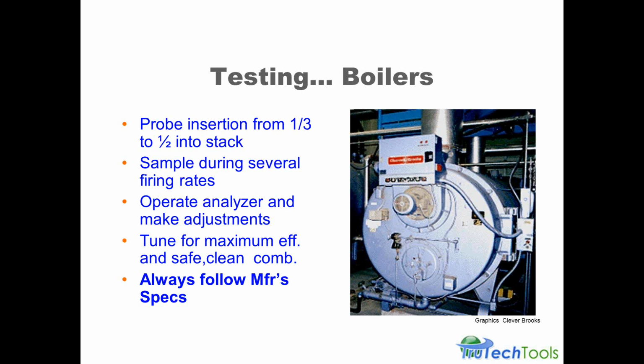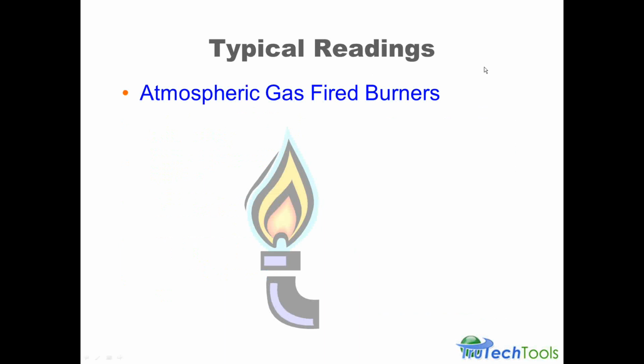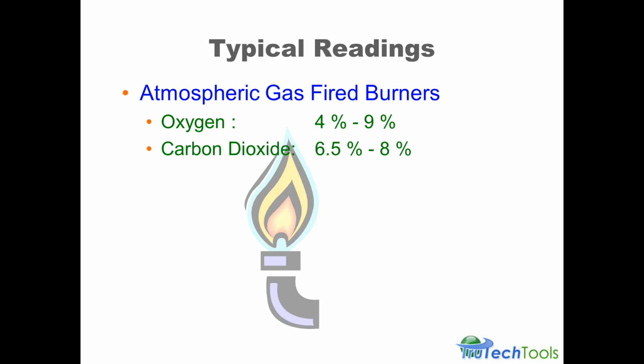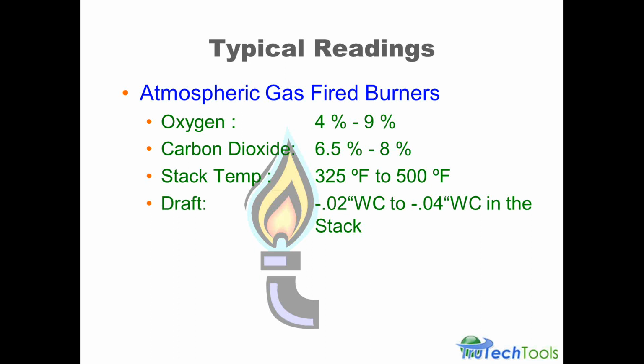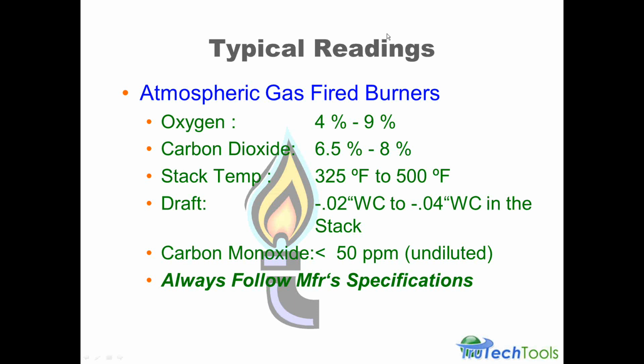And as we say all the time, you do definitely want to follow the manufacturer specifications to optimize the equipment and to have it installed correctly. So when we get to atmospheric gas-fired burners, some of the typical readings you might see would be 4 to 9% oxygen. If you remember back to that chart that we drew, showing the oxygen on the excess air side, this is where you'd be measuring 4 to 9% oxygen. The carbon dioxide measurement would be between 6.5% and 8%, and that would be usually calculated from your analyzer. Stack temperatures 325 to 500. Draft in the 0.02 or 2/100ths of an inch water column to 4/100ths of an inch water column. Negative draft. Remember we talked about draft being negative at that point after the dilution. Carbon monoxide usually less than 50 ppm when measured on an undiluted basis. And again, refer back to the manufacturer's specs to provide the most keen information for the equipment you're testing.